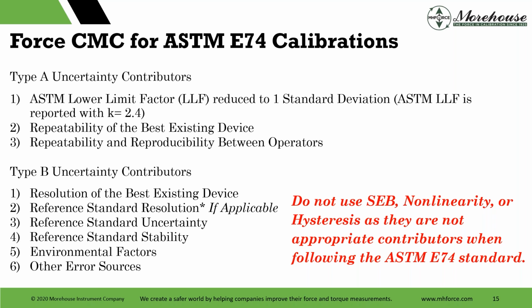A repeatability of the best existing device and repeatability and reproducibility between operators. Those are all type, potentially, most of them are type A. Type B, resolution of the best existing device, reference standard resolution, reference standard uncertainty, reference standard stability. Stability can be type A or B, and environmental factors and other error sources. Stability would be type A if I had like 10 years worth of data and I did statistical analysis on it. We could likely move it up and getting to some more advanced stuff here.